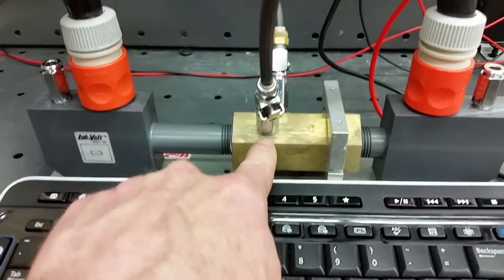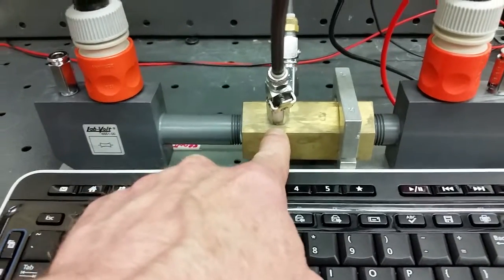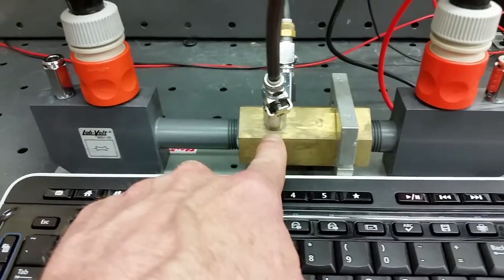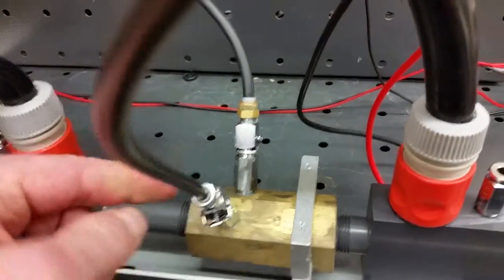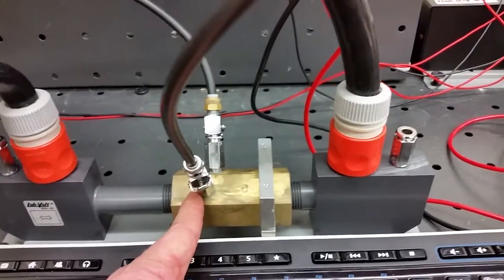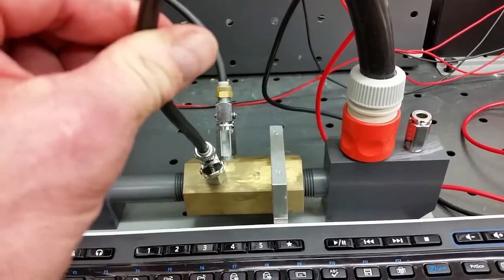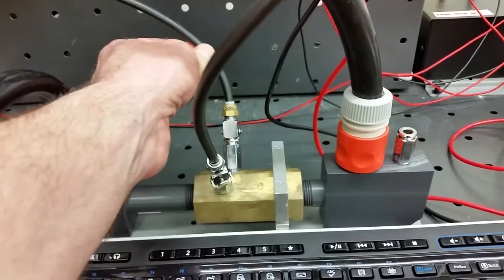The venturi tube takes the diameter of the pipe and reduces it to create a restriction. That creates a high pressure port on the inlet and a low pressure port at the throat. Because the flow diameter is reduced, the static pressure decreases and the flow speed increases, based on Bernoulli's principle.